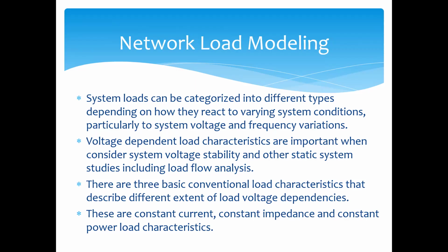Voltage dependent load characteristics are important when considering system voltage stability and other static system studies, including load flow analysis. There are three basic conventional load characteristics that describe different aspects of load voltage dependencies. Some loads have real and reactive power consumption that depend on the system voltage at that point. Conventionally there are three types of load models: constant current load model, constant impedance load model, and constant power load characteristic. Let me discuss more about that.